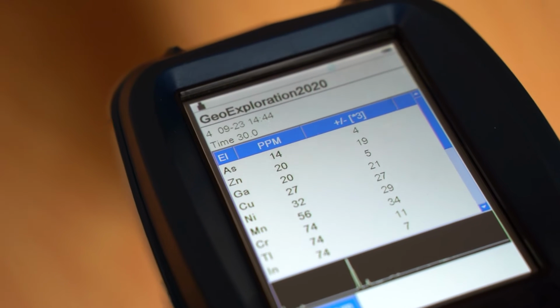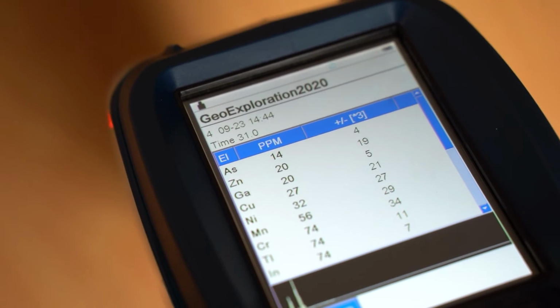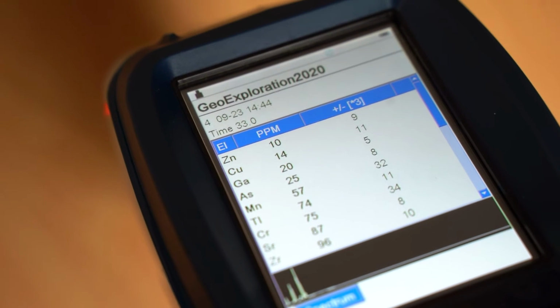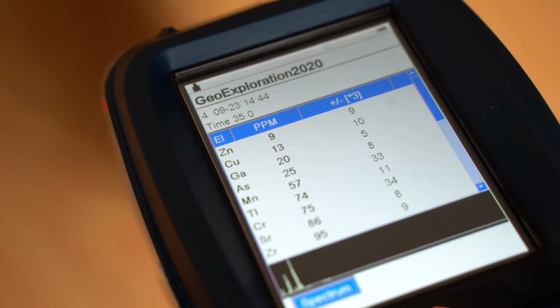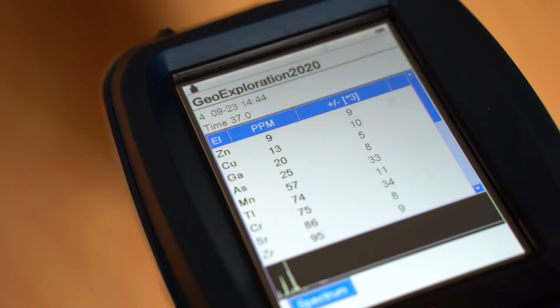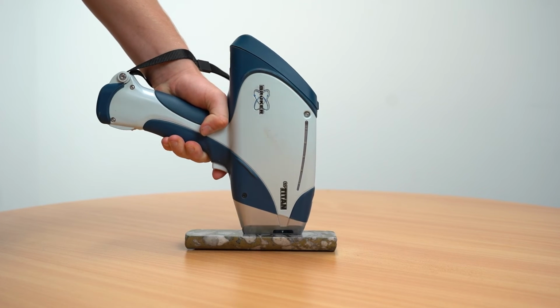one scan. So for example, let's use the geo-exploration calibration on the Bruker S1 Titan. This calibration has 3 beam phases that are recommended to be set at 20 seconds per beam, making for a total analysis time of 60 seconds. If you were then to only run the scan for 25 seconds and then stop, the instrument would not have collected the optimized data for all the elements.